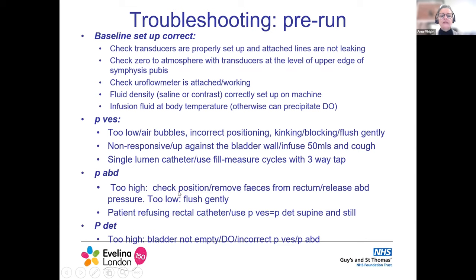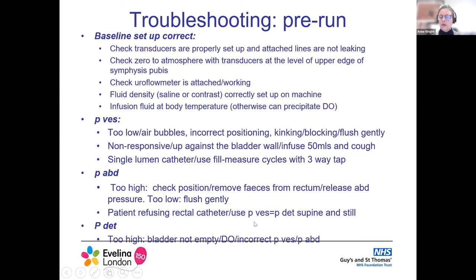Regarding P-ABD: if it's too high, check positioning — is it in a contracted anus or a wodge of feces? Have you blown the balloon up too high without a good enough slit? Release the pressure. If it's too low, flush gently. Neurogenic children who don't get good anal closure can give too low P-ABD. If your P-DET is too high, fundamentally check P-VES and P-ABD are correct first. It might be that the bladder is not empty with poor compliance, that the child is mid-void, or that there is sustained detrusor overactivity. You cannot have a negative P-DET in theory, so you need to correct all of that.